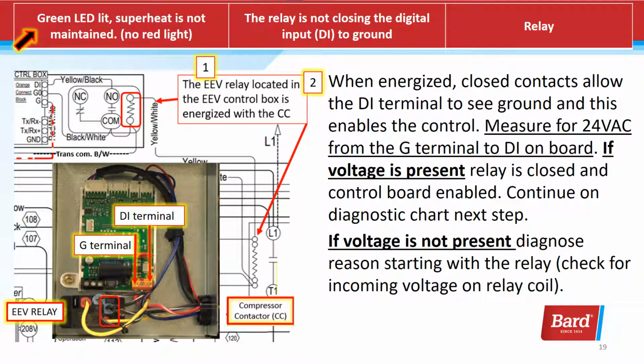The next step is to verify that the relay is closing. When energized, the closed contacts allow the digital input terminal to see ground and enable the controller. In the lower left corner, there is a picture with an orange terminal strip. The green light is on, indicating that we have 24 volts on the control.